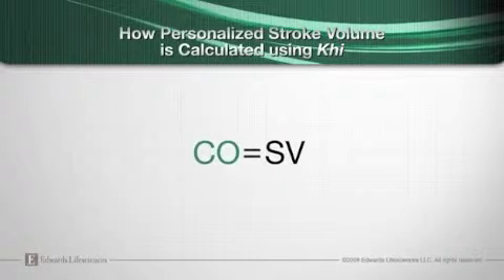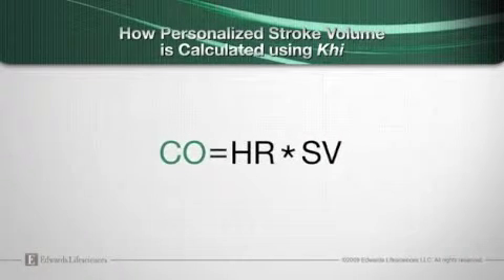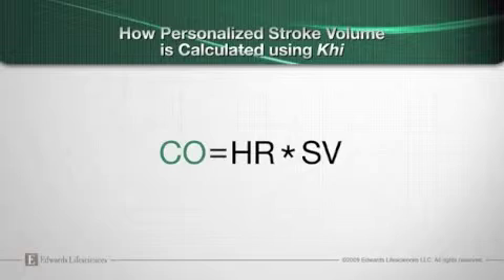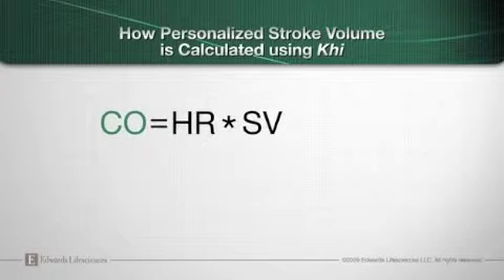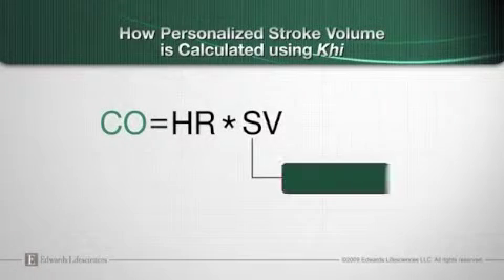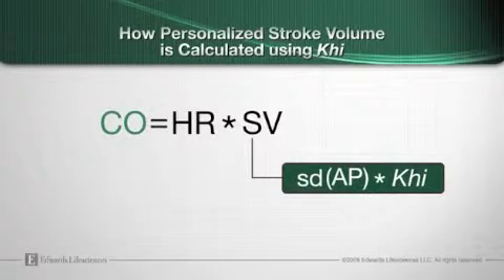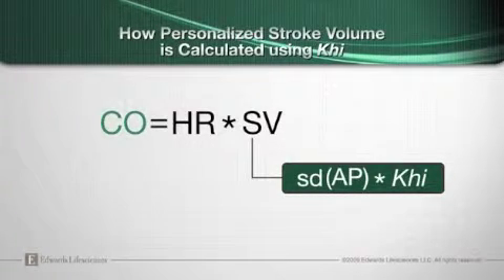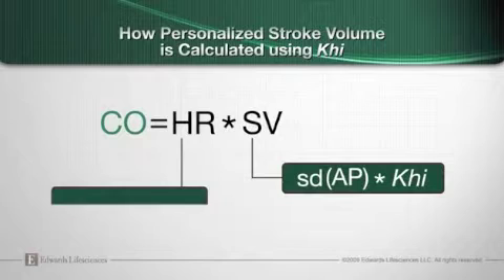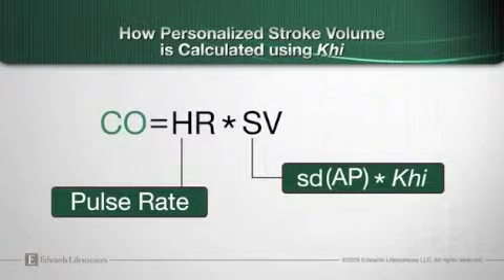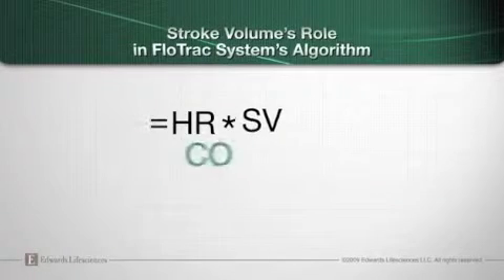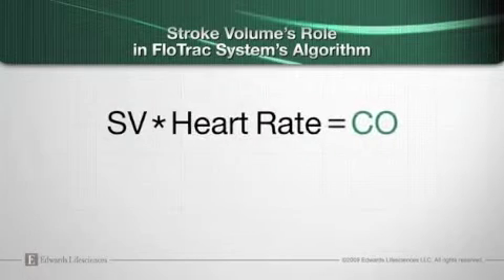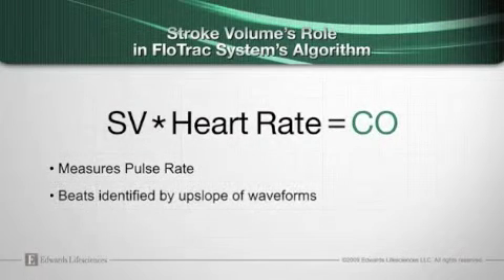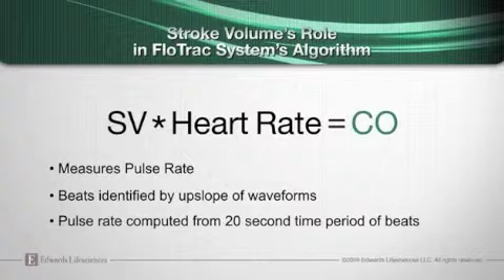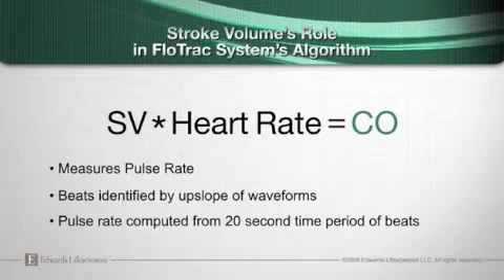Cardiac output is calculated by multiplying heart rate times stroke volume. The FloTrac algorithm calculates stroke volume by multiplying the standard deviation of the arterial pressure, SDAP, signal against Khi. Pulse rate is calculated from the arterial pressure signal. When stroke volume is multiplied by heart rate, which is measured by the pulse rate that is computed from a 20-second time period of beats, the result is cardiac output.